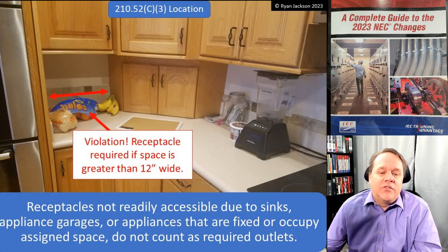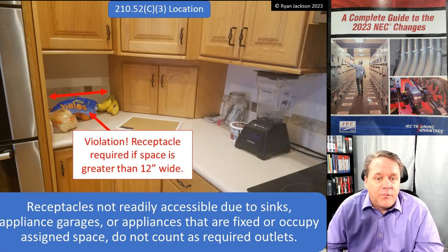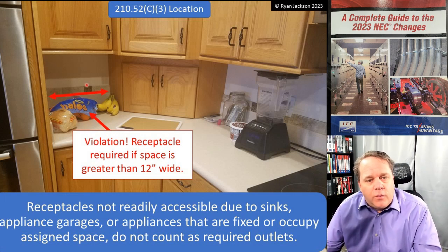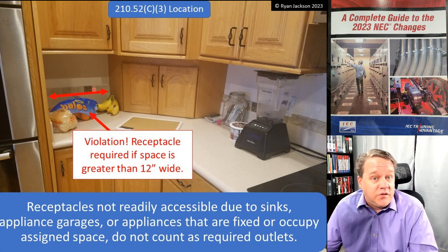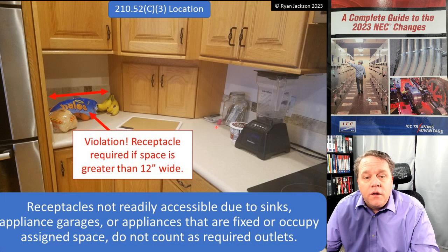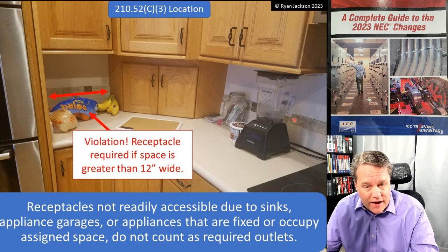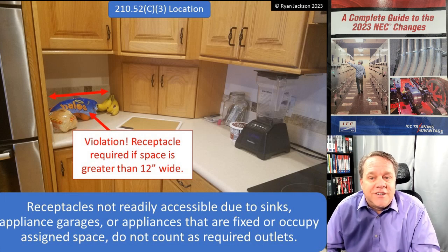Finally, 210.52C3 states that receptacles that are not readily accessible due to sinks, appliance garages, or fixed appliances occupying assigned space do not count as required outlets. In this photo, an appliance garage breaks the measurement — butt the tape into the ovens on the left, pull right, and if that countertop space exceeds 12 inches, a receptacle is required. One is needed on each side of the appliance garage, and it looks like behind the blender there is one on the right. Big changes in 210.52.